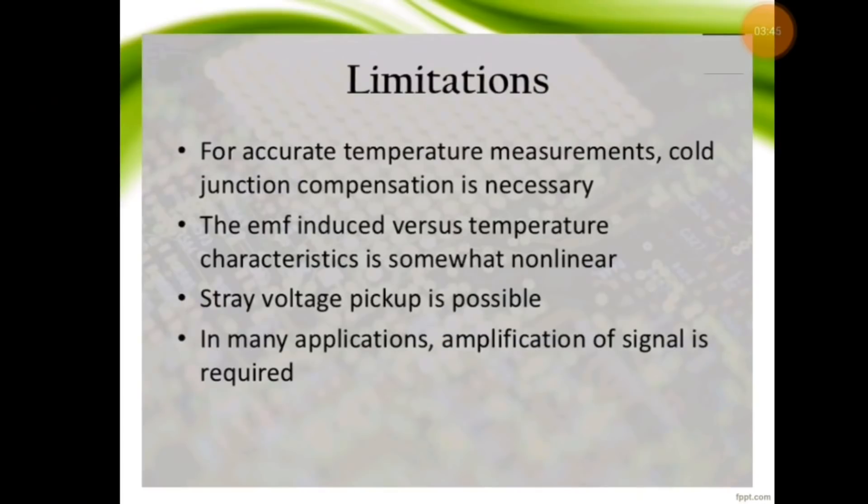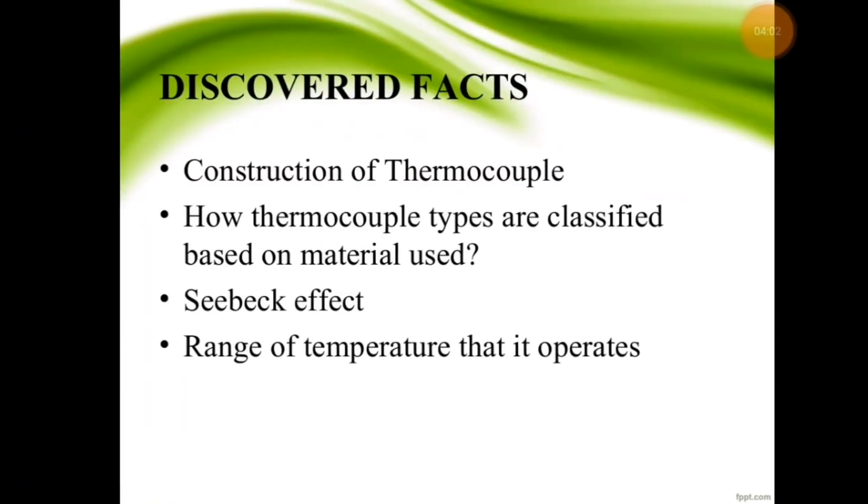Every object has its own limitations. For accurate temperature measurements, cold junction compensation is necessary. The EMF induced versus temperature characteristics is somewhat non-linear. Stray voltage pickup is possible and in many applications, amplification of signal is required. Discovery facts include construction of thermocouple, how thermocouple types are classified based on material used, Seebeck effect, and range of temperatures that it operates.